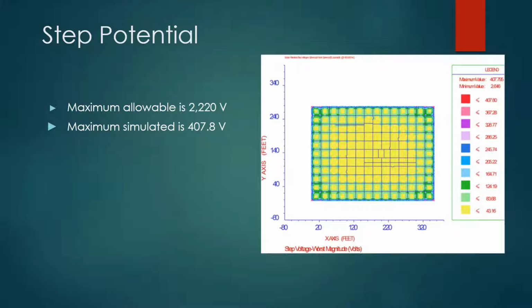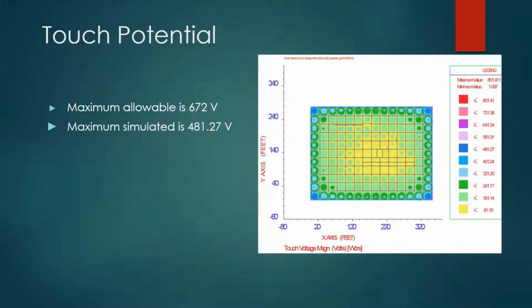This is a problem with the software because the software cannot simulate an infinite plane or a semi-infinite plane like the Earth is. So the area where two lines come together, where there's nowhere else for current to go, are going to have higher voltage levels. And we kind of see the same thing in the corner with touch potential, where the corners have a significantly higher voltage level than everything else. For touch potential, the maximum allowable is 672 volts. The maximum simulated is 481.27. Like I said, there's higher voltages on the legend, but the area that we care about, where most of our equipment is located in the middle of the substation, is primarily yellow or below a touch potential of 81.1 volts, which is well within the safe limits.